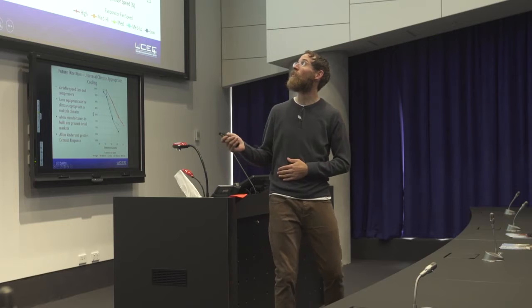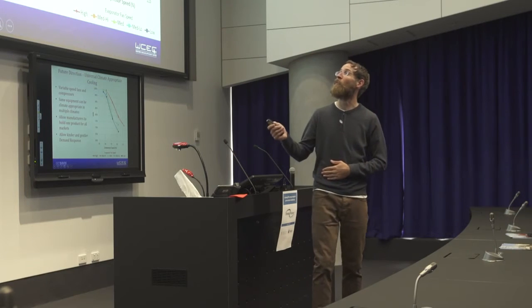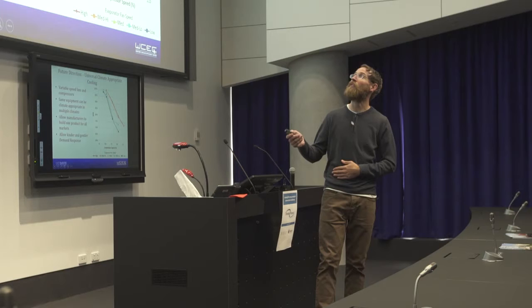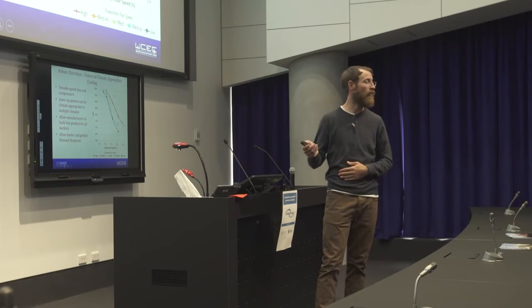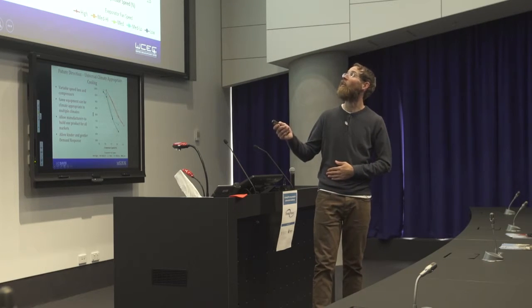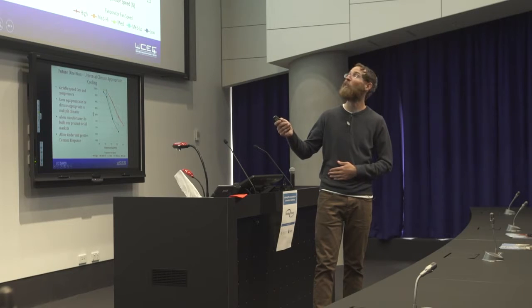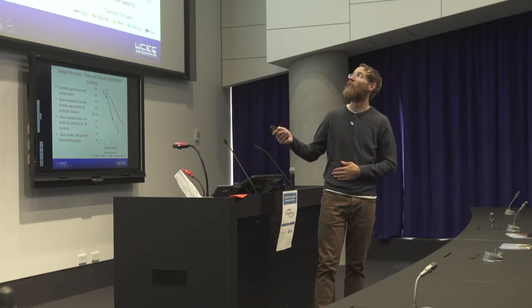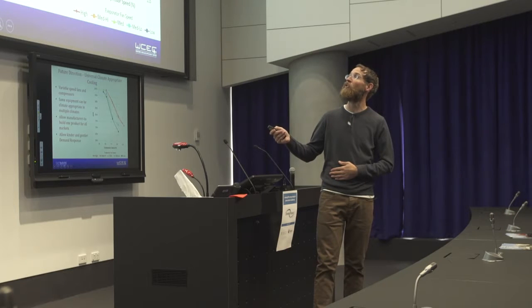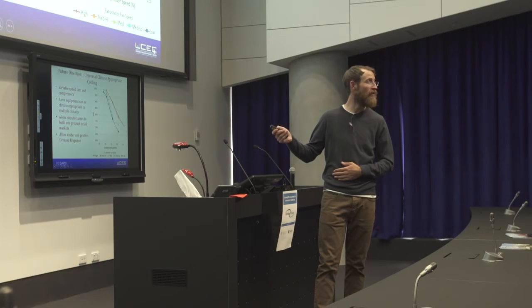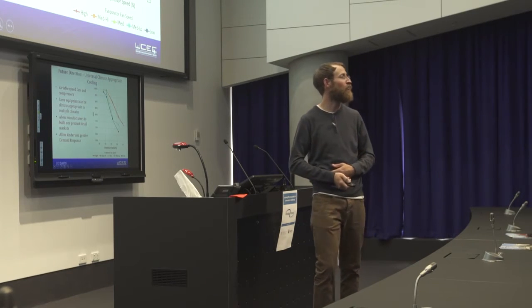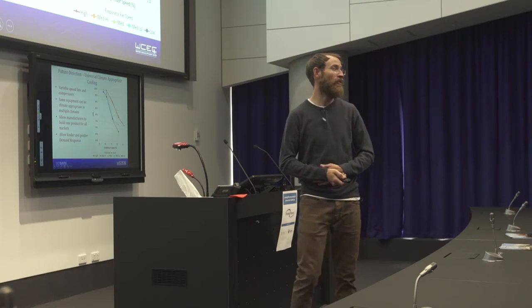These are some examples of laboratory tests that show different fan speeds, different compressor speeds, and the sensible heat ratio that we're able to gain. So while a normal variable speed system might be set up to operate here, and when the compressor speed's running at about 100%, they run a sensible heat ratio of around 70. If we tune things appropriately with the fan speeds, we can actually increase the sensible heat ratio and improve the sensible coefficient of performance for the machine considerably.